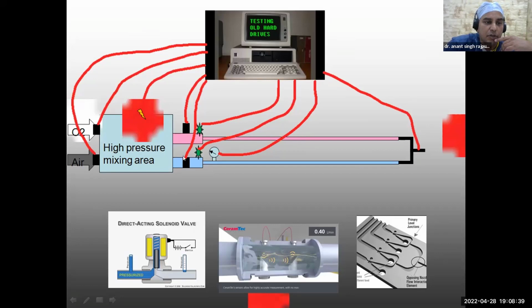At the same time, besides these two valves, there are flow sensors. The green color ones are flow sensors in both inspiratory as well as expiratory. Then there is a pressure sensor, okay? Pressure sensor in the expiratory side of the ventilator. All these are continuously feeding the responses to the ventilator, and the ventilator is continuously assessing all this and manipulating itself to give whatever modes and other things we are doing.